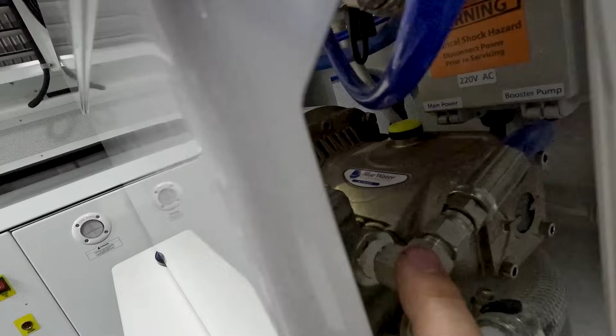So high pressure output pressure is 0. The high pressure pump, which is this one right here, the high pressure alarm sensor, which is this guy right here, I disconnected it and the alarm cleared. So now I'm going to try to run it without this and see if I can get it to make some water. If I can't get it to make water, I might have to pull this apart and pull that sensor out of there. Let's see what happens.